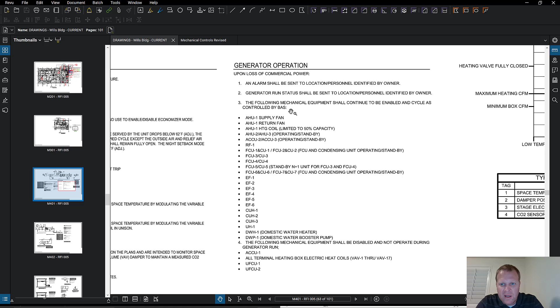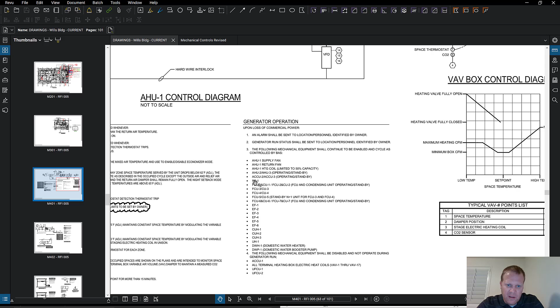So the generator, like I said, we talked about the generator a little bit, but starting up the generator is not the same as running it through its sequence of operation. When we tripped the generator and cut power and the generator turned on, did it continue to enable all this stuff right here? That's kind of like the test, right? And that's an entire system to make it work rather than just a couple components, right? Lots of different components on this that work together as a complete system, right? The FCUs, the exhaust fans. Anyway, hopefully that made sense.